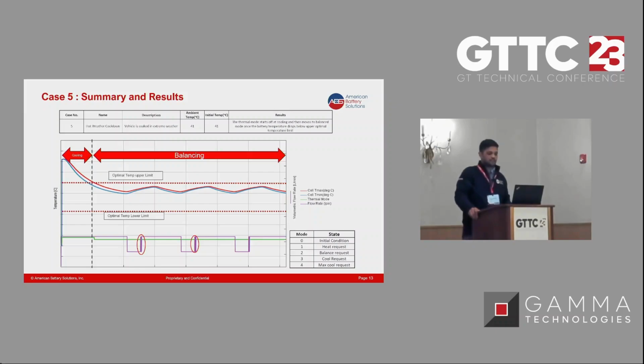This is where we found the issue highlighted in the red circle: the flow rate was fluctuating up and down, with the BMS requesting a flow rate that fluctuated over a very short period of time. The main purpose of this kind of testing is to identify these issues and rectify them before testing in the actual model, and we were able to identify and rectify it.